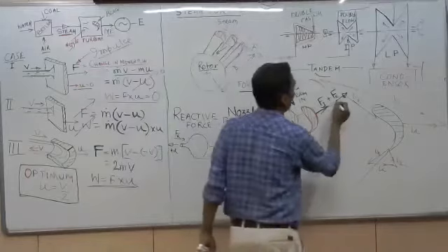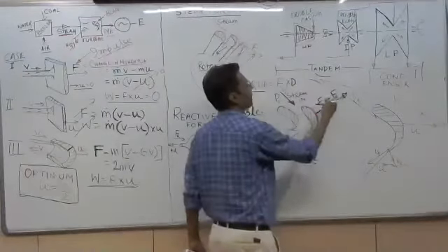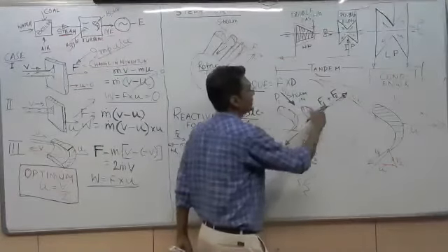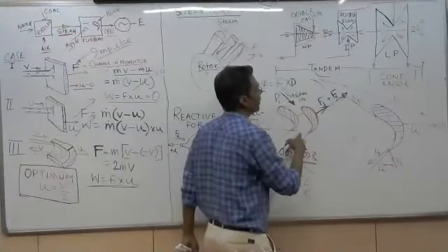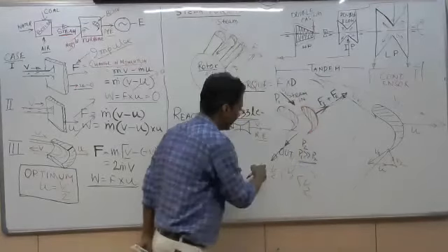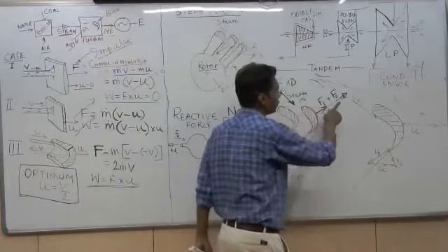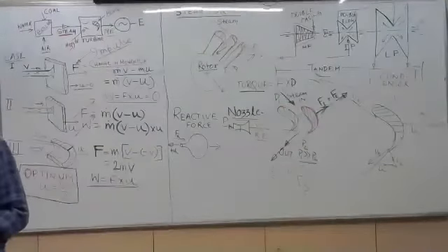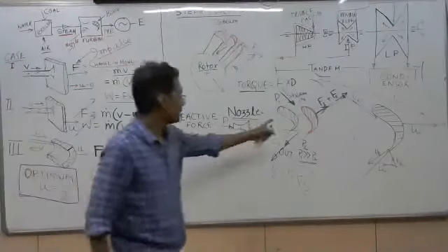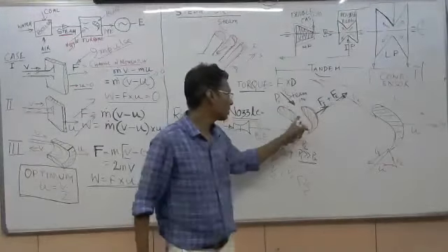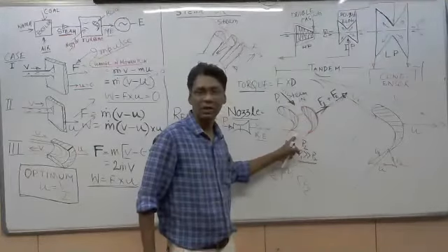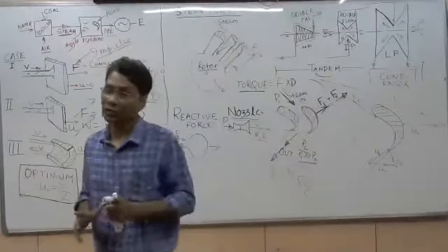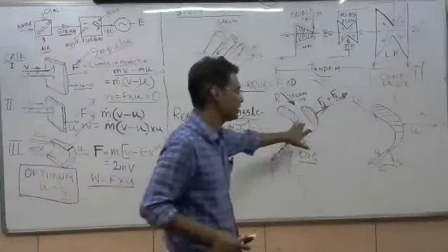More velocity means there is one component that is called F reaction. That reactive force we are getting. Due to change in momentum, there is the impulse force, and due to increase in velocity, there is a reactive force. There are two component forces. The force is increased by the design of the blade, in such a way that the reactive blade profile gives a nozzle-shaped area, and we are getting two kinds of forces. So that is the impulse-reactive blade design.